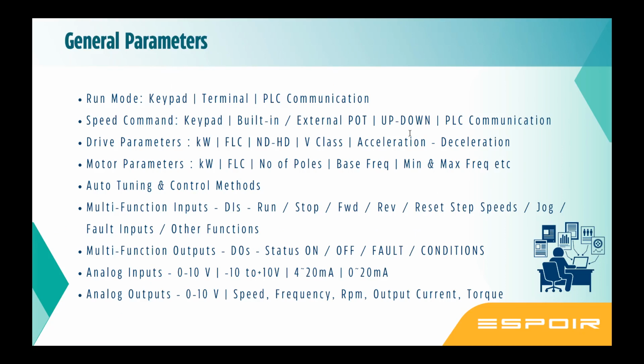Now, the second aspect is speed command. How are you going to change the speed? You can change the frequency from the keypad. Go to a particular directory, change the parameter and set, it will adopt. There is a built-in potentiometer given in smaller VFDs. You can just configure that, and then use it like your electronic fan dimmer. You can change the speed of a motor by using that knob.